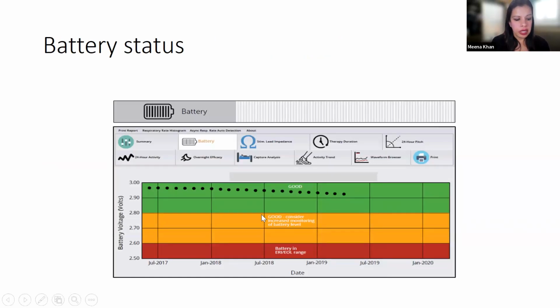So this is what their battery status can look like. Green means they're good; they have plenty of battery life. When it starts hitting into the yellow, we probably need to see them every few months, so every 2 to 3 months, to keep an eye on this. And when it starts approaching the lower end of orange to red, they need to be scheduled for a battery change out.